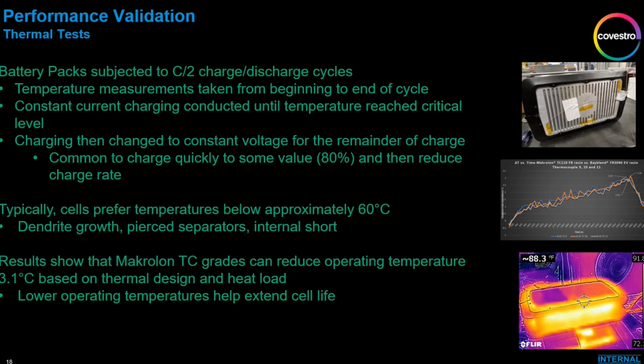Is that significant? Well, there are a lot of different ways of judging whether or not a thermal performance is good or bad. But one criterion says that you lose half your cell life for every 9 degrees C above ambient that the pack operates. So if you use that as a criterion, 3 degrees out of every 9 degrees is a pretty significant number. So dropping the overall operating temperature by 3 degrees Celsius can influence the overall cell life, overall pack life. Another key criterion is delta T across the pack. And we also took a look at that and found that with the TC materials, we were able to achieve a delta T across the pack of 3 degrees Celsius or less.